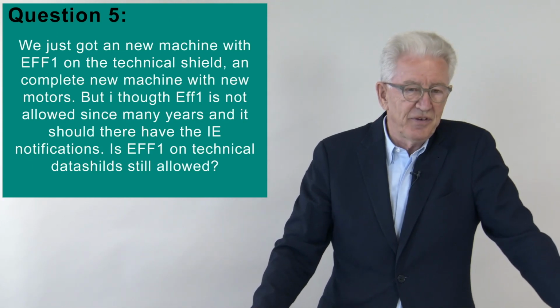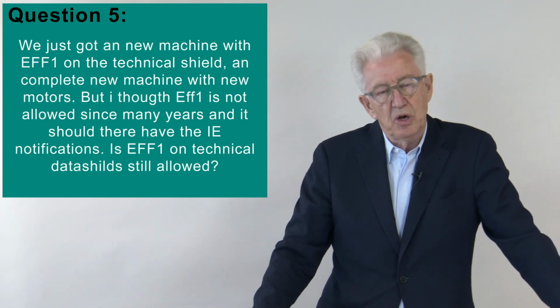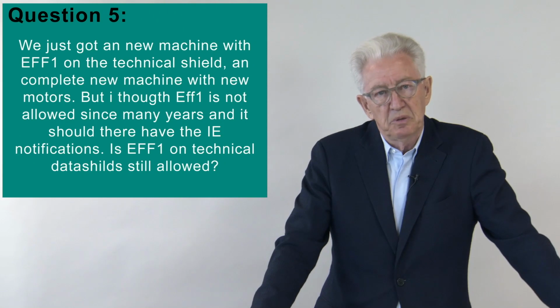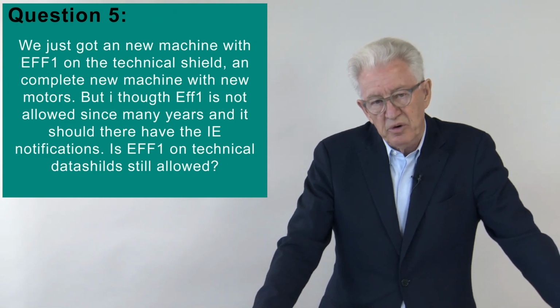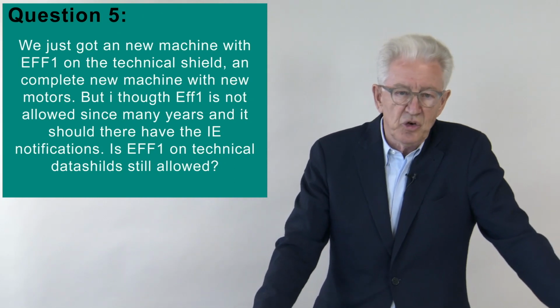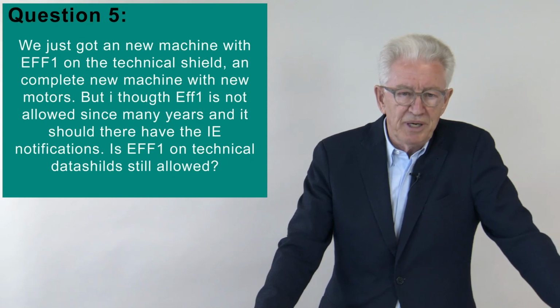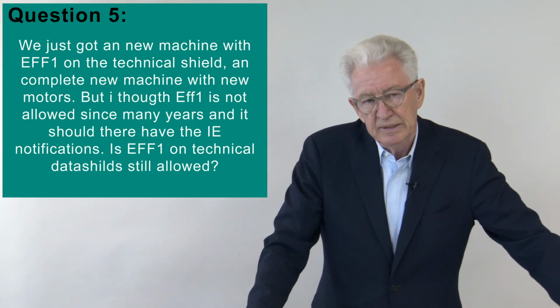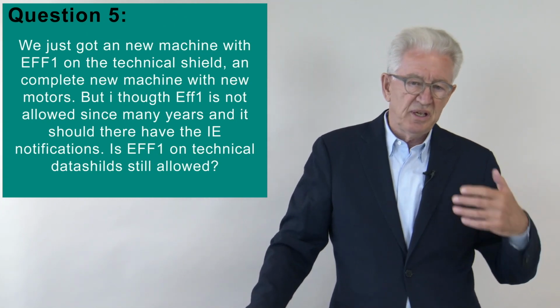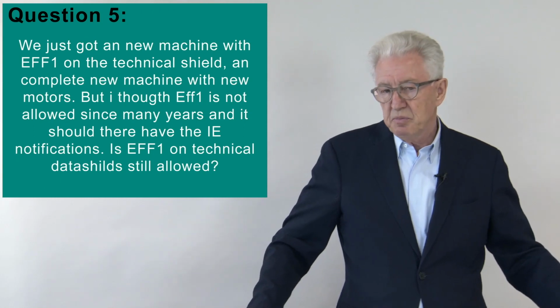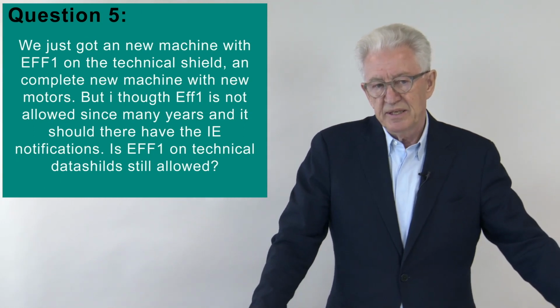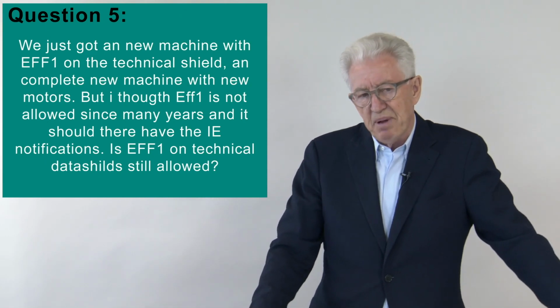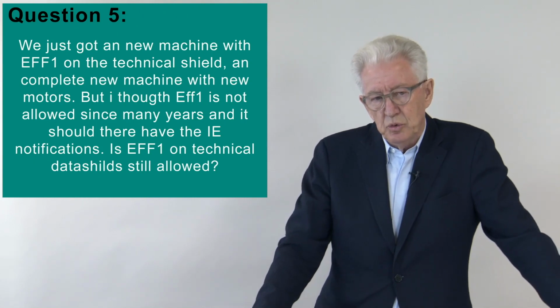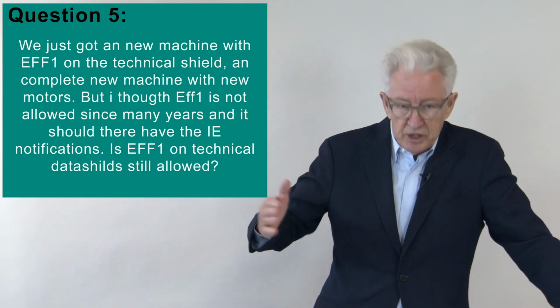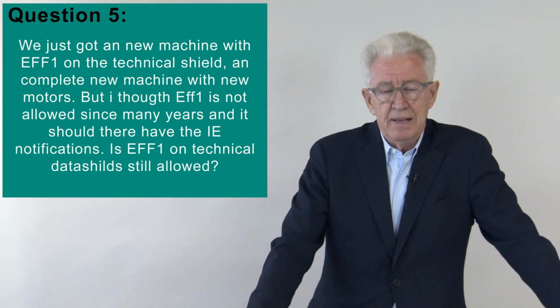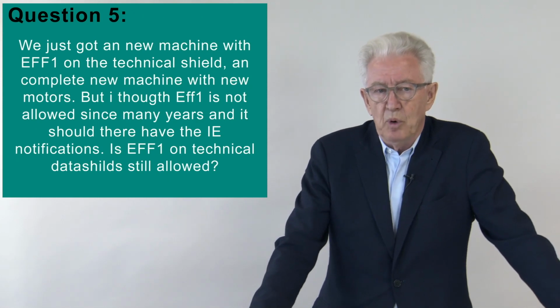You find a lot of anachronisms in the motor world, and as everybody knows, on a rating plate you can put almost any information you want. EFF1 or F1 was a European voluntary agreement between the European Motor Manufacturer Association, CEMEP, and the European Union. It was the EF1, EF2, EF3 system. EF1 is more or less equivalent to the new IE2. The system was launched in the 90s and was officially abandoned once the IE classification - IE1, IE2, IE3, IE4 - came in.